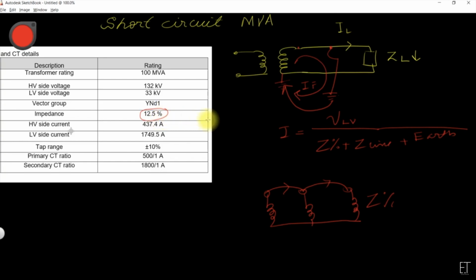As a thumb rule, as the voltage of the transformers increases, for example for a 132 by 11 kV transformer, the percentage impedance is 12.5%. For another transformer of 11 kV by 400 volts, for example a distribution transformer, the percentage impedance drops to 5% or 4%. And for a 220 kV by 132 kV transformer, the percentage impedance will be higher, for example 18% to 20%.